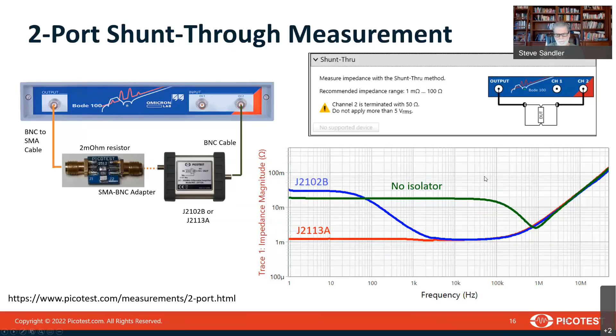And in this plot, I'm showing how that measurement is impacted by different isolators. You can see the dramatic difference, especially below a kilohertz. Without any isolator at all, you can see up to about a megahertz, but with an isolator, below about a kilohertz. One of the reasons that it's really important for us to measure our own capacitors is because often data doesn't go low enough in frequency. I'll talk a little bit about that later.